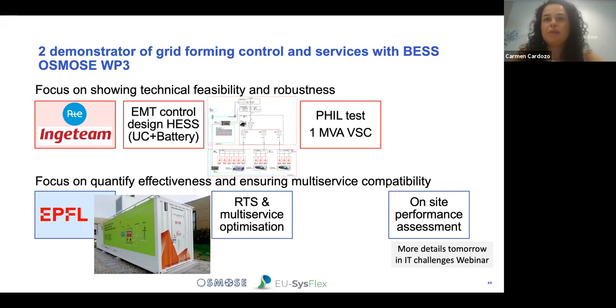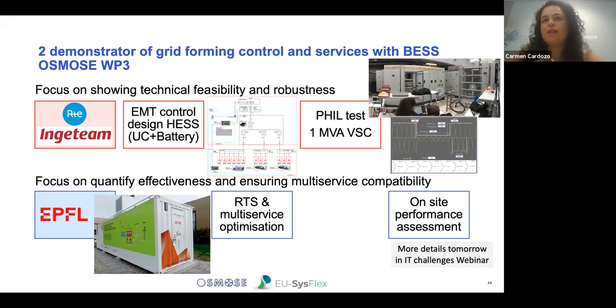I know the image is a bit small, but the idea in the small square is below. You have on the left-hand side batteries, and then you have 2 groups of ultra caps. Then you have 3 DC-DC converters that interface the DC bus with the different energy sources. And then you have the AC-DC converter, and here is where we put the grid forming control. After a phase of design, we have simulation and control design.